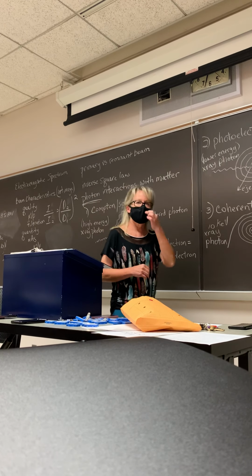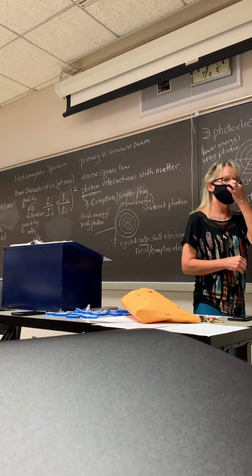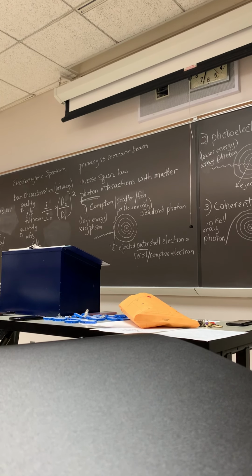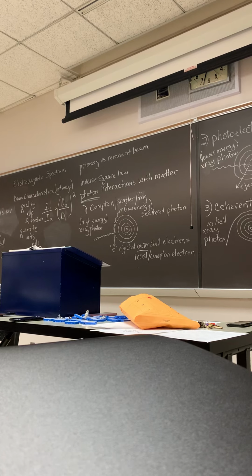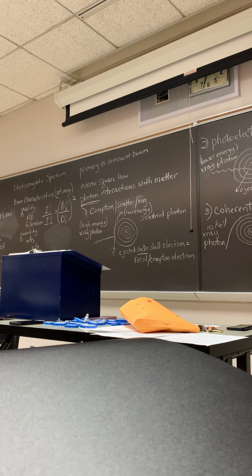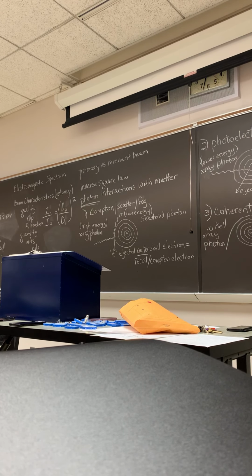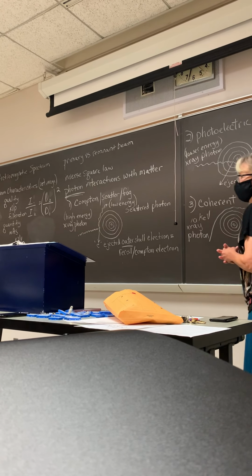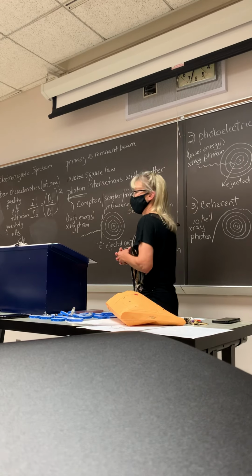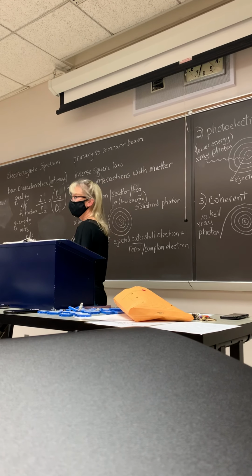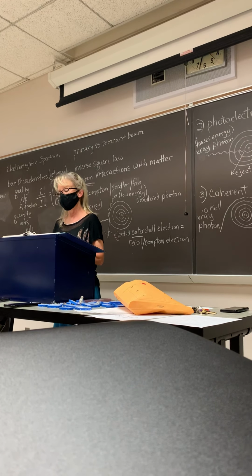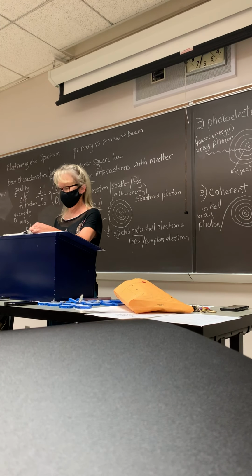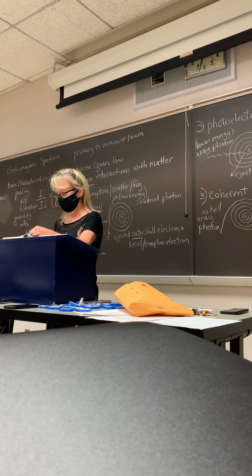Okay, secondary barriers, they protect against secondary radiation. So any wall above 7 feet. The ceiling, you usually can never aim the X-ray tube at the ceiling. The control booth is a secondary barrier. And that has to be at least 1/32 of lead.